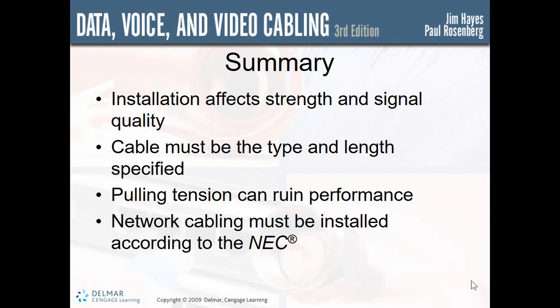So in summary, both strength and signal quality are affected by installation quality. Cables must be the type and length specified. Even too much pulling tension on a cable can ruin its performance, because if you have 16 twists per inch, when you're done pulling too tightly, you might end up with 8 twists per inch, which will degrade the performance of the cable.